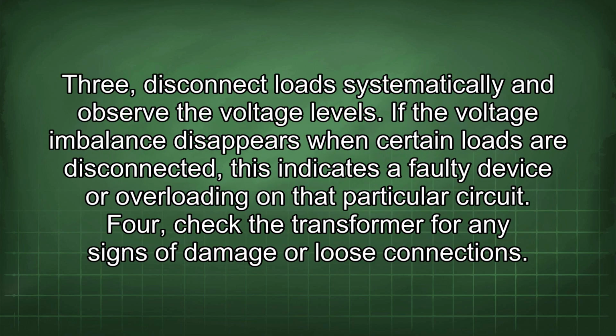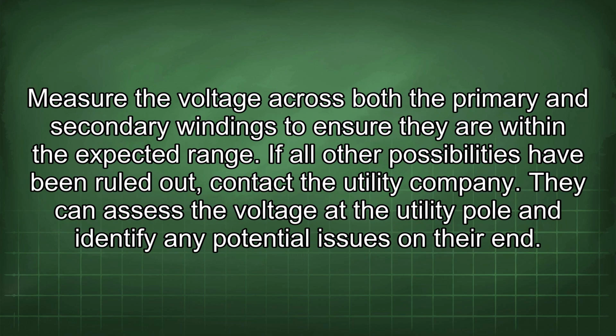3. Disconnect loads systematically and observe the voltage levels. If the voltage imbalance disappears when certain loads are disconnected, this indicates a faulty device or overloading on that particular circuit. 4. Check the transformer for any signs of damage or loose connections. Measure the voltage across both the primary and secondary windings to ensure they are within the expected range. If all other possibilities have been ruled out, contact the utility company. They can assess the voltage at the utility pole and identify any potential issues on their end.